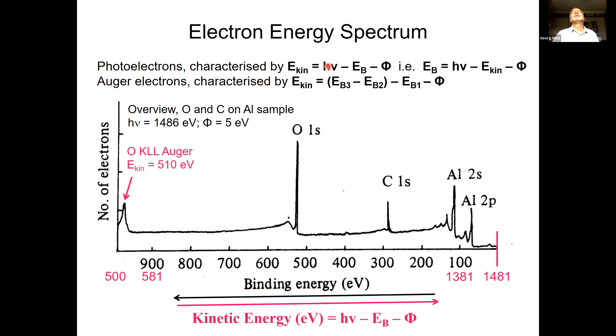Modern analysers combine the hemisphere with an electrostatic lens in front that also acts as a retarding field. We always use the same pass energy, but reduce the energy of incoming electrons by applying a voltage across this lens, allowing convenient scanning of the kinetic energy range. This setup gives us a well-defined photon energy and a means of measuring the intensity of photoelectrons as a function of kinetic energy.